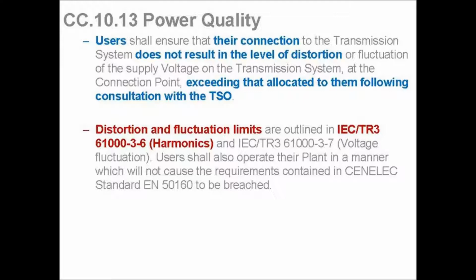We've got a clause in there on power quality. Power quality is more than harmonics, it also has flicker and some other good stuff in there as well. But it basically puts the onus on the users to ensure that their connection doesn't exceed the level of distortion allocated to them by the TSO, which in this case is Eirgrid. And there's something similar in the distribution code. And then it states that these limits are based on 61000-3-6, which we've already just talked about.